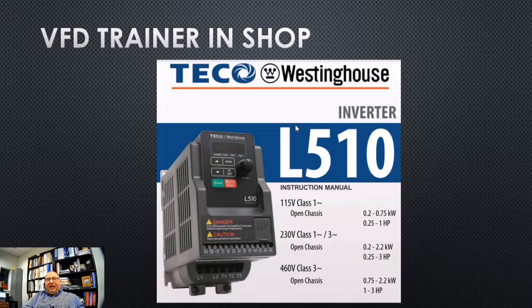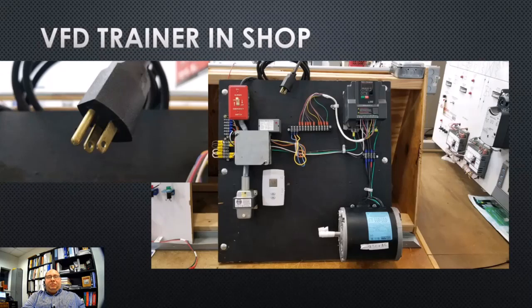This is how people could put a VFD on a lathe, a wood spinning machine, where they can take a 115 volt motor, remove it, and put a 230 volt 3-phase motor in there, anywhere from 1/4 horse to 1 horsepower, and it uses a normal 115 outlet. Pretty neat, but the pulse modulation on the 3-phase side remains the same. Same type of theory, same technology. Terminology might be different between Westinghouse and the other brands, but ultimately we're going to set it up the same way. This is what you're going to look for in the shop.